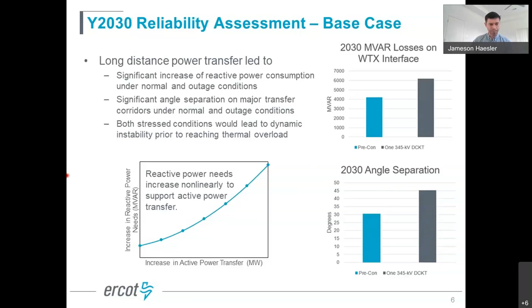We see the same challenge with angle separation, starting in pre-contingency at an already slightly discomforting 30 degrees, to a much more discomforting angle separation of 45 degrees post-contingency. What these two conditions illustrate is that this is going to lead to dynamic instability prior to reaching any sort of thermal overload.